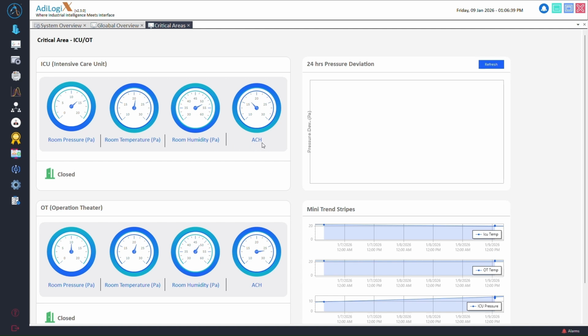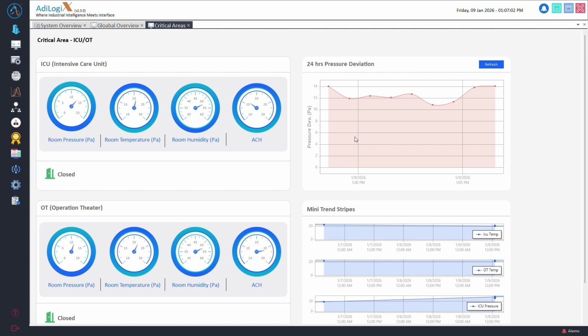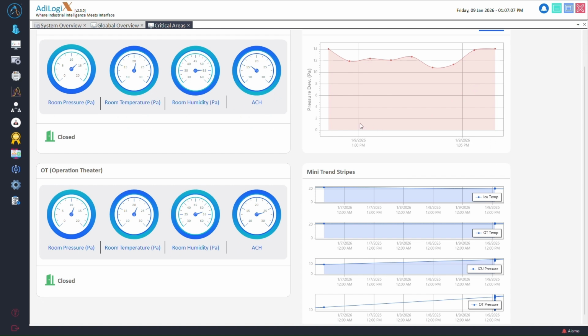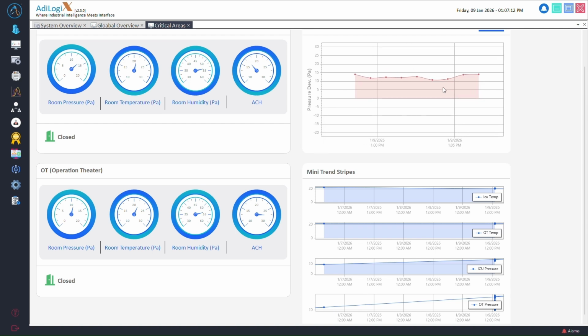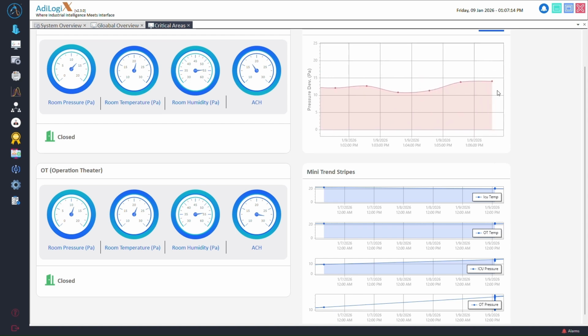All values are validated live, no estimation, no delay. Below the gauges, door status is monitored in real time. Every open or close event is logged because even a few minutes of door mismanagement can compromise pressure integrity. On the right, the 24-hour pressure deviation trend provides complete historical traceability. Each data point represents an actual pressure reading. Spikes immediately indicate potential breaches, such as door openings or airflow disturbances. This timeline forms the backbone of compliance audits.